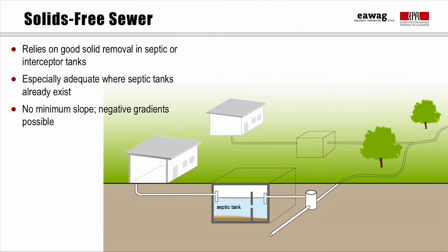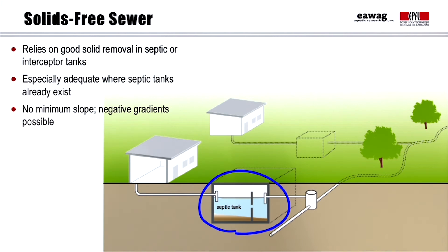The last option is the solids-free sewer system. As its name indicates, the specificity of this system is that solids are separated before entering the sewer system itself. This is done at the house level, for example with single-chamber septic tanks. Removing the solids dramatically reduces the risk of deposition and plugging, so there is no need for a minimum flow velocity or a minimum slope. The system can even bear negative slopes as long as the downstream end is lower than the upstream end.